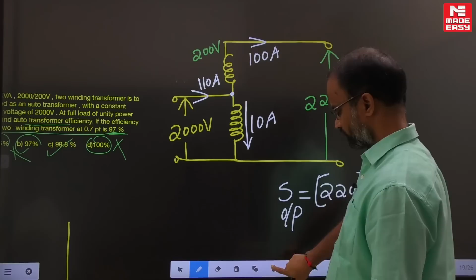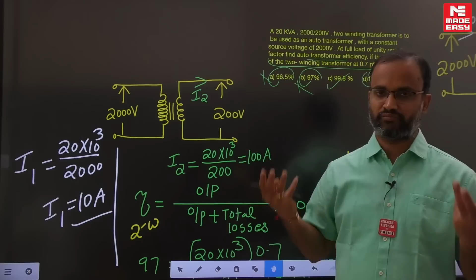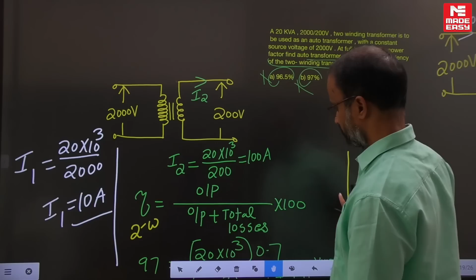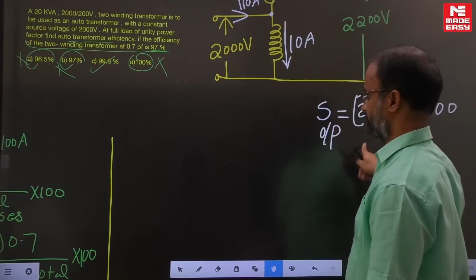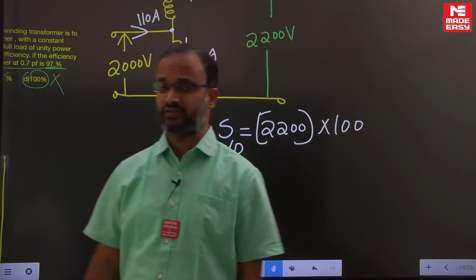The current circulating in the 200 volts winding and the 2000 volts winding, in the two winding transformer, is exactly the same current. Here also the current is 10 amperes, and here it is 100 amperes. Since the magnetic core is the same, the same current circulates in the windings. So we can conclude that the losses in the two winding transformer are exactly the same losses we use for the auto transformer.